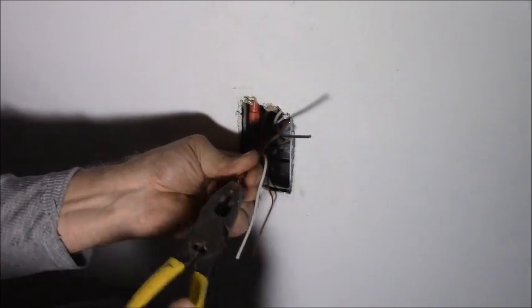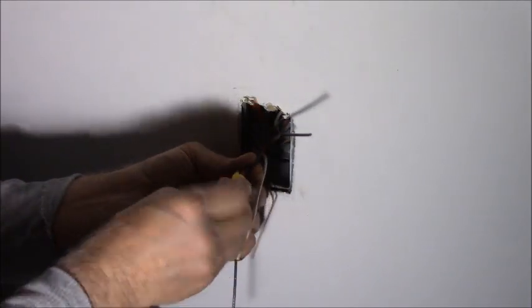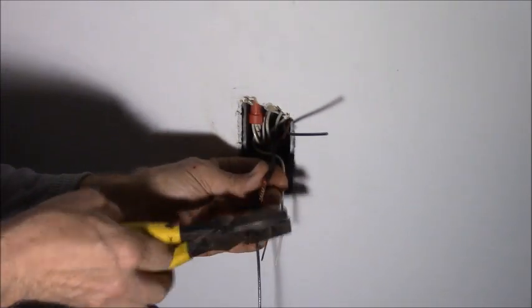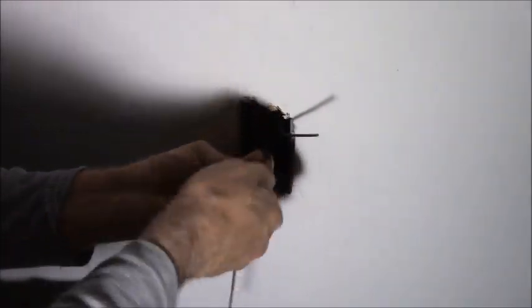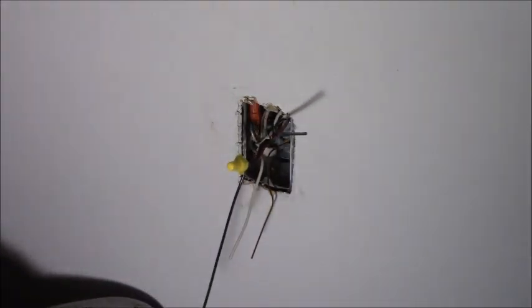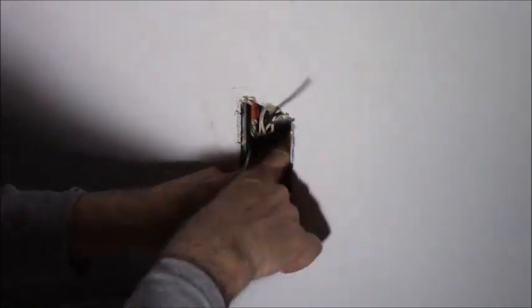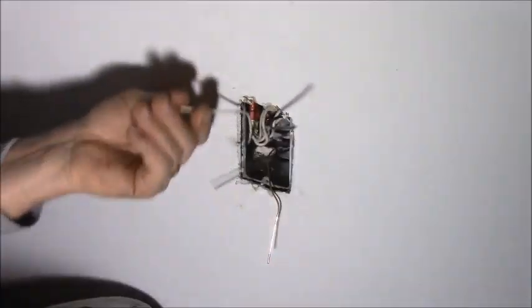That's beautiful. I think I can cut this wire nut a little shorter. See, they put this 4-inch box in here because the code does call for more space in the junction boxes with the more stuff you have in there.